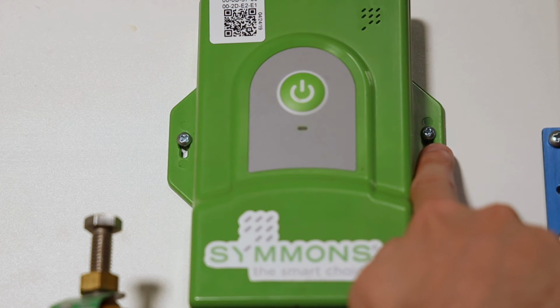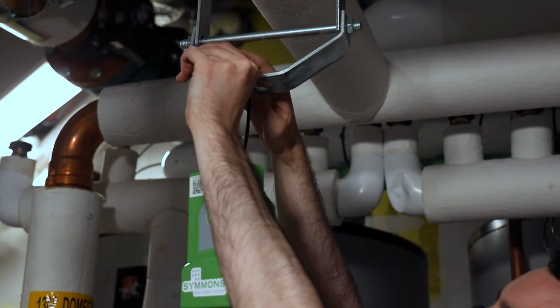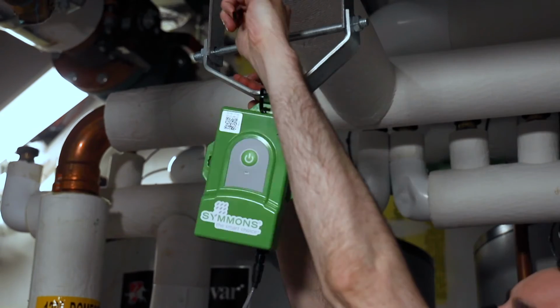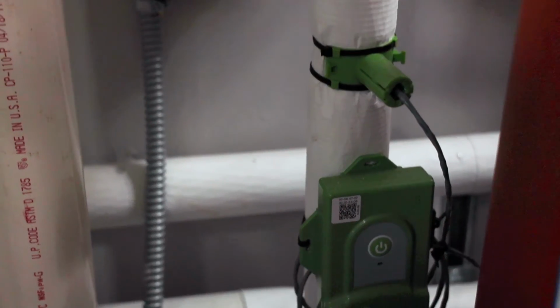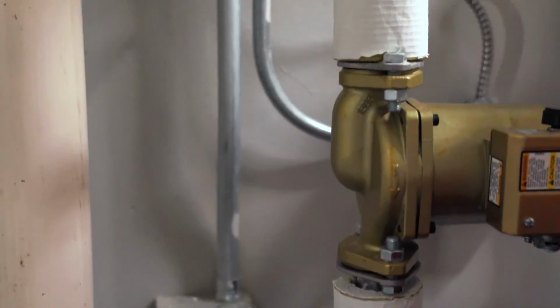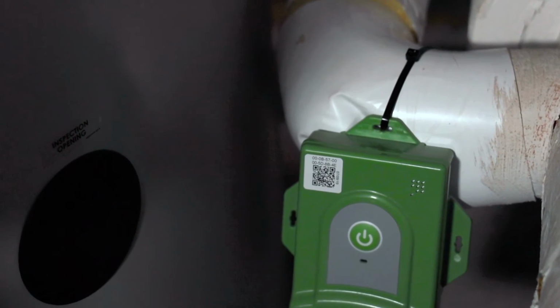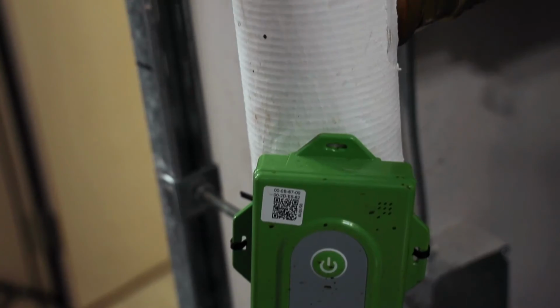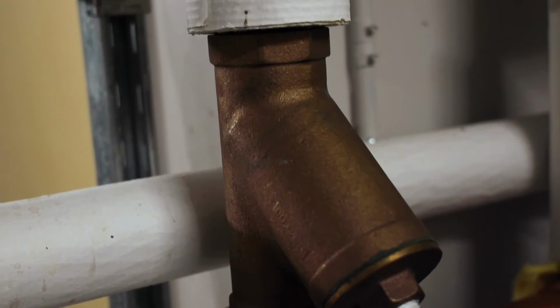You can attach them to the walls with screws, or you can use the cable ties to attach them to the insulated pipes, brackets, or hangers. The modules are splash-proof, but not waterproof, so make sure they're mounted in a dry location since they also sense ambient temperature. They also include electronics and small internal antennas, so don't mount them to hot or metal surfaces.